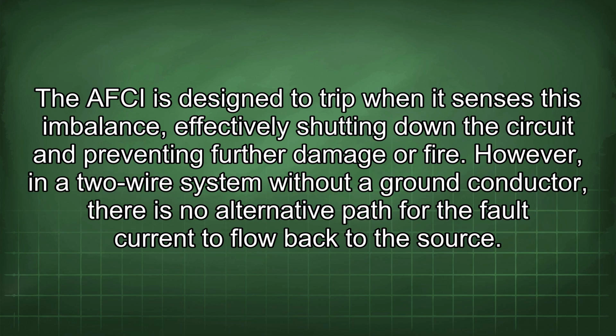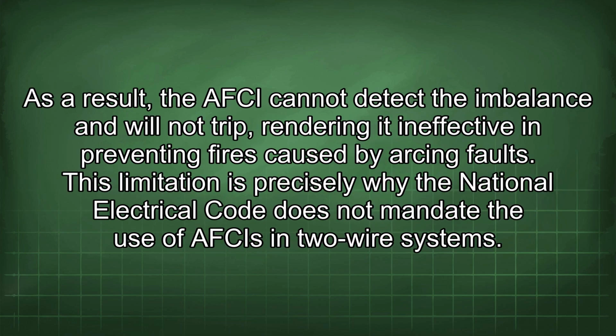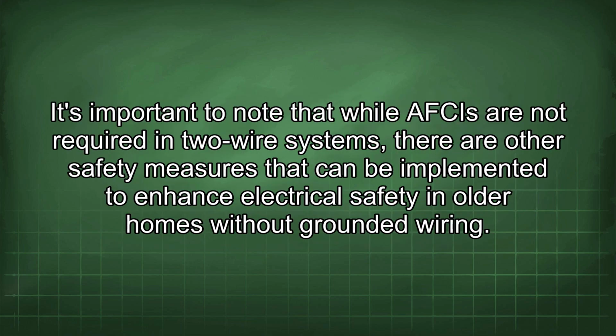However, in a two-wire system without a ground conductor, there is no alternative path for the fault current to flow back to the source. As a result, the AFCI cannot detect the imbalance and will not trip, rendering it ineffective in preventing fires caused by arcing faults. This limitation is precisely why the National Electrical Code does not mandate the use of AFCIs in two-wire systems. It's important to note that while AFCIs are not required in two-wire systems, there are other safety measures that can be implemented to enhance electrical safety in older homes without grounded wiring.